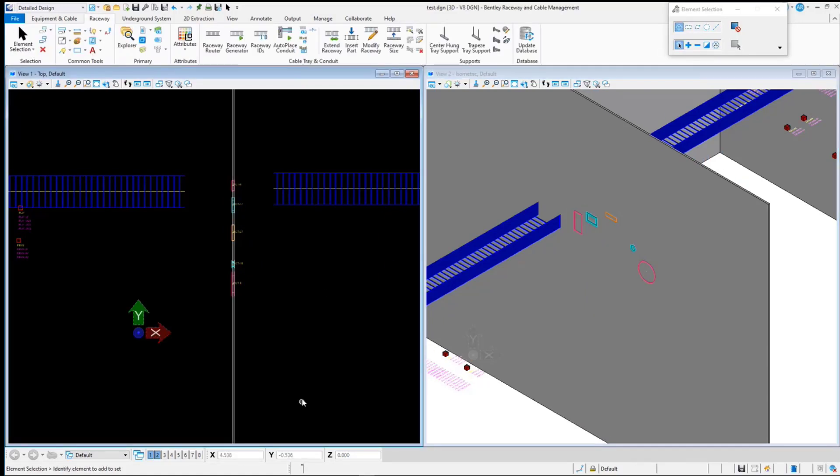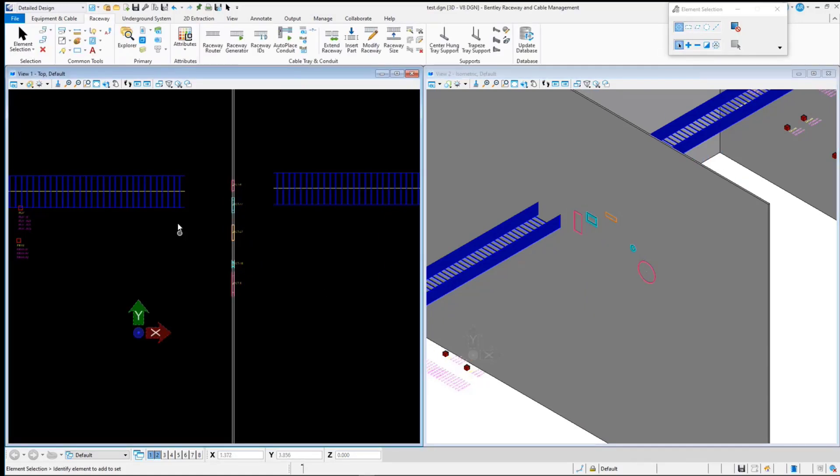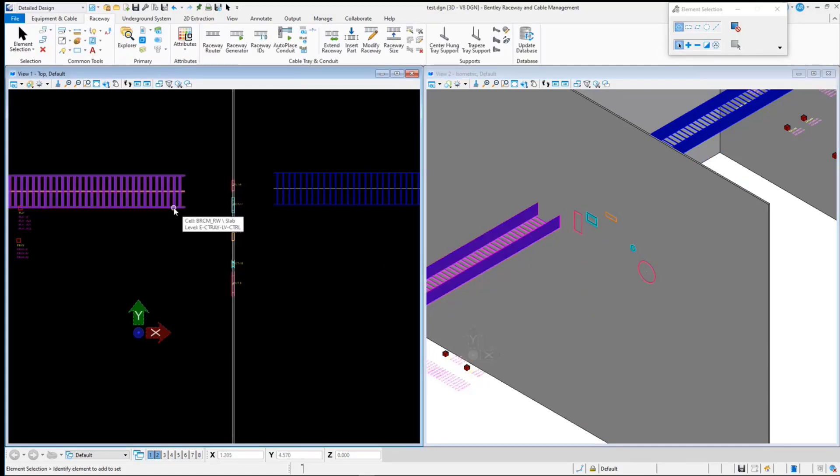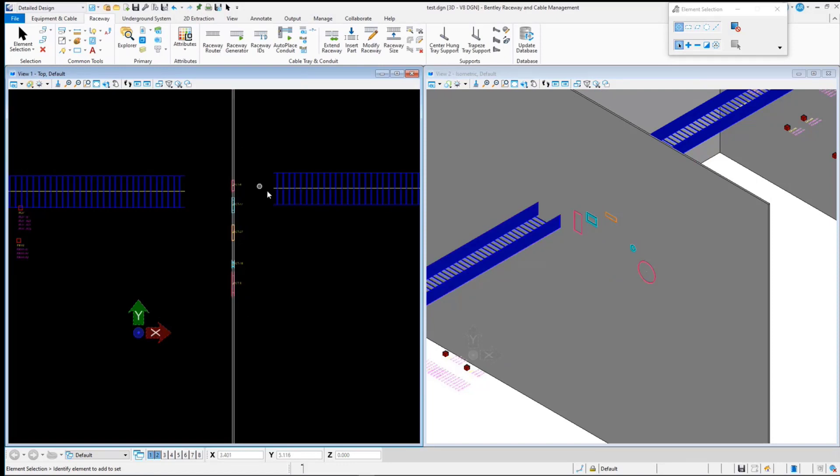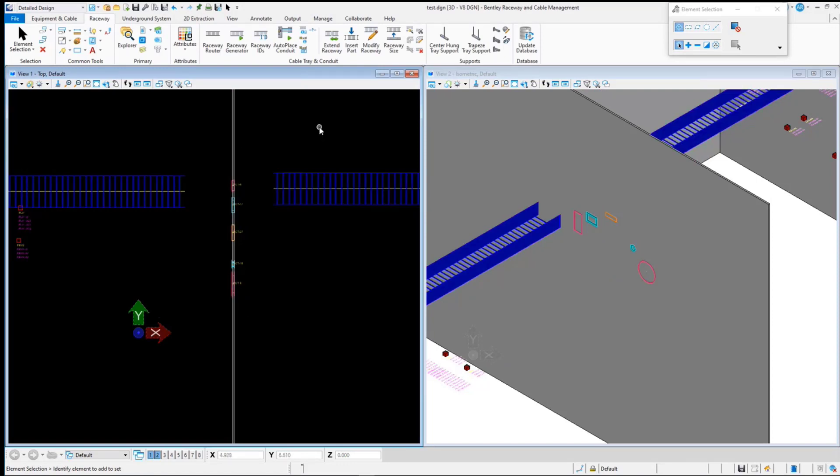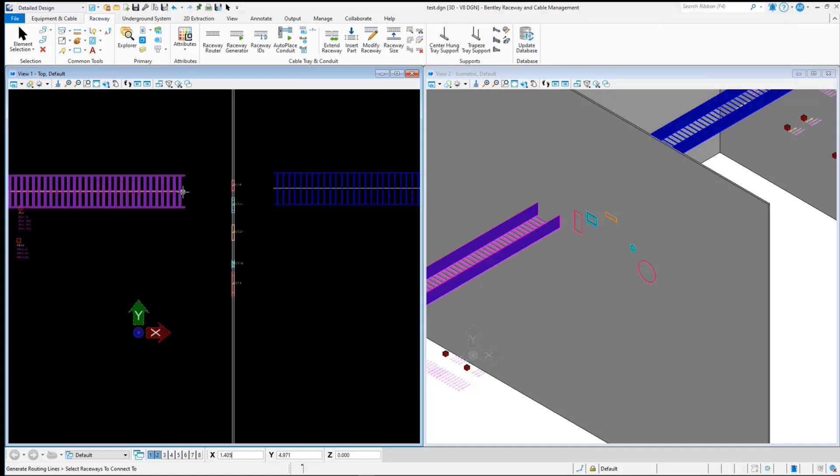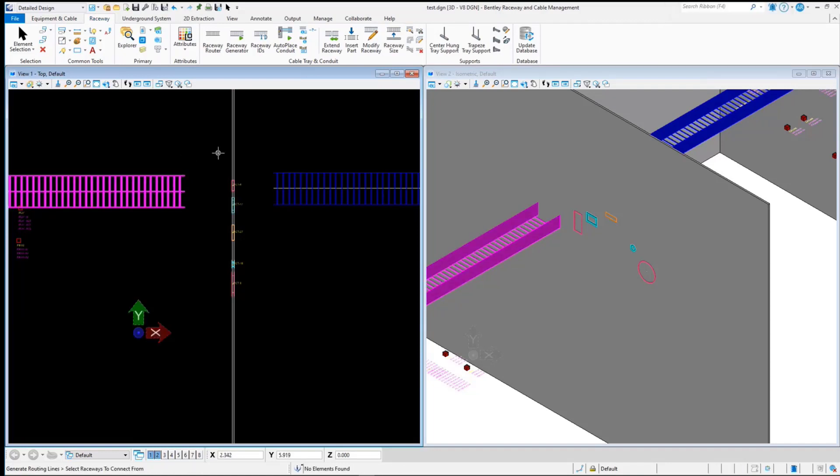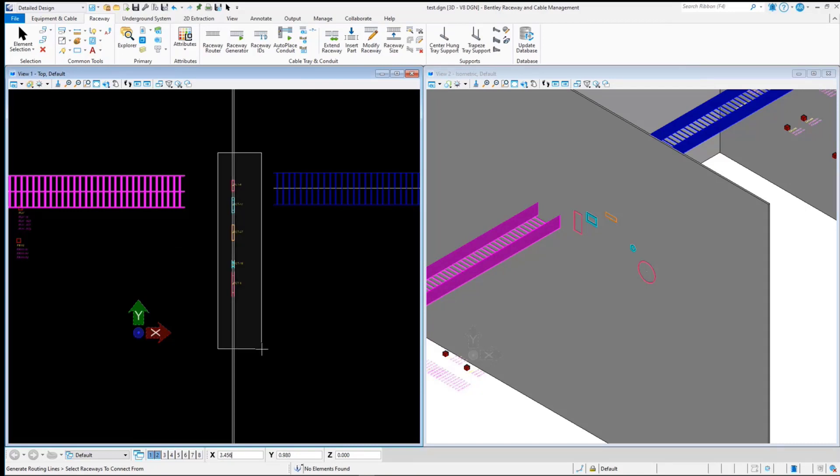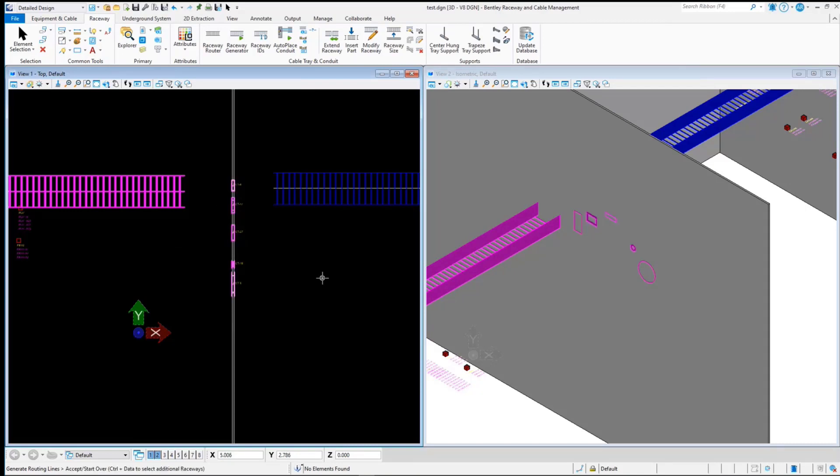The next step will be to create a connection between the raceways and the transits with the help of Generate Routing Lines. Select the Generate Routing Lines tool, select the raceway, and you can select the transits all at once or one by one. It will create routing lines between the raceway and transit. Repeat the same step for the other raceway.